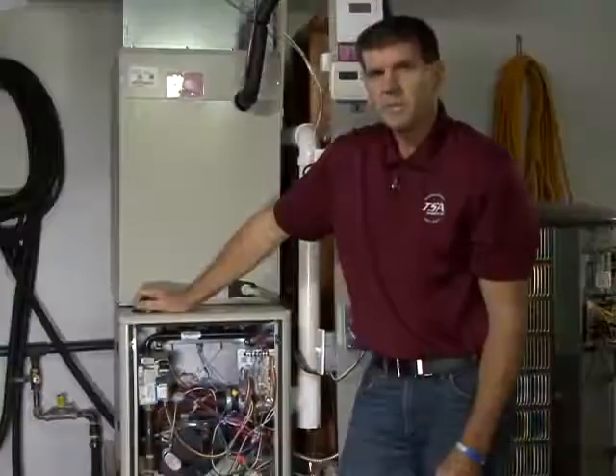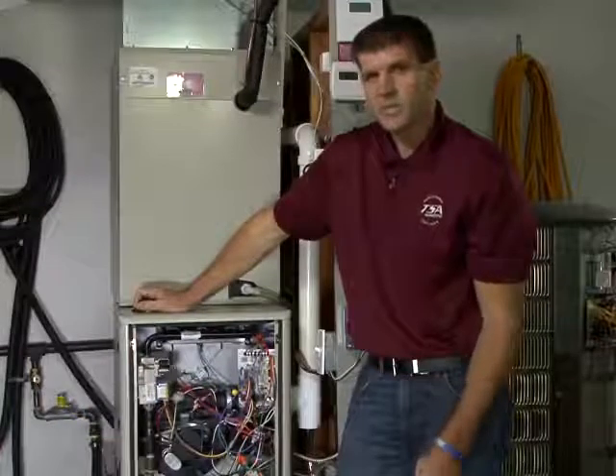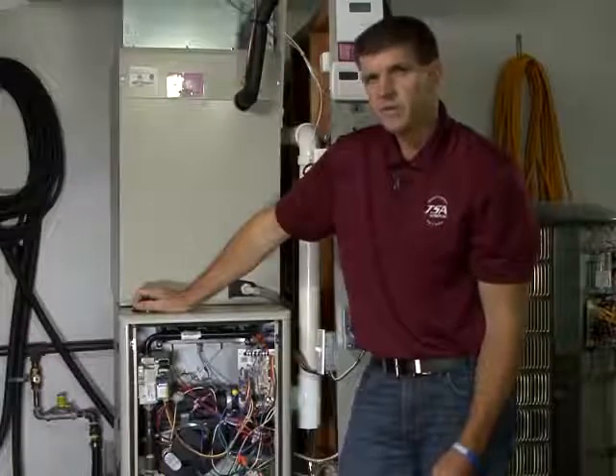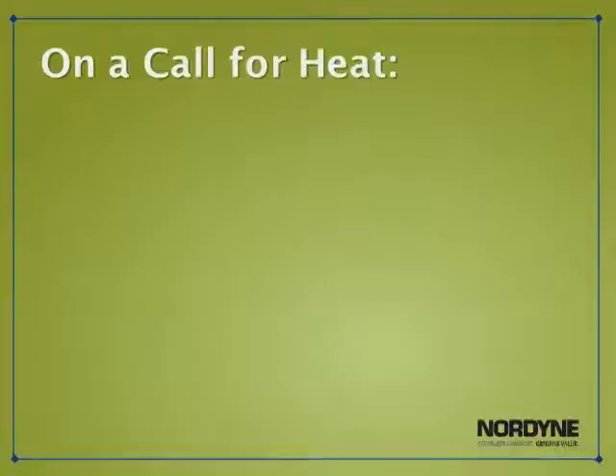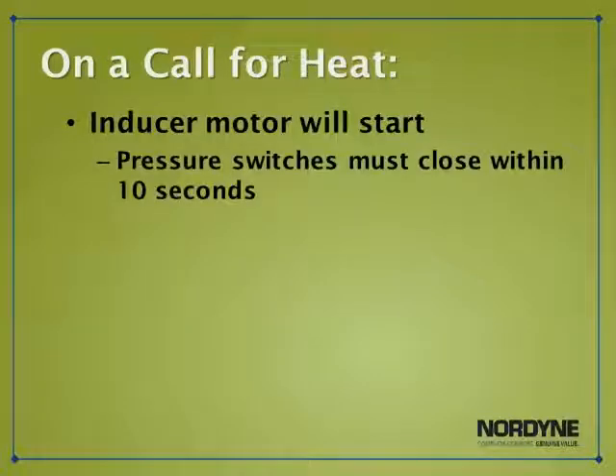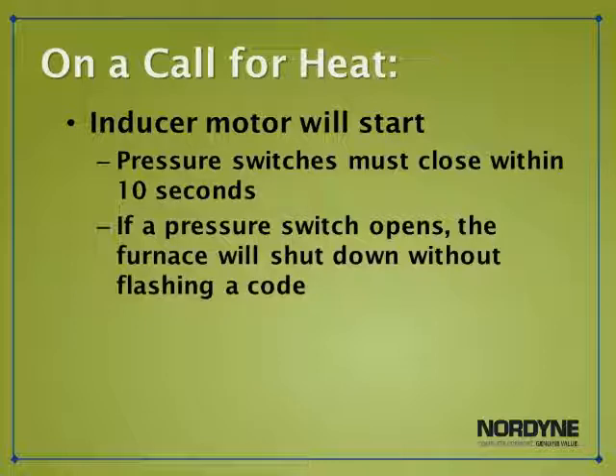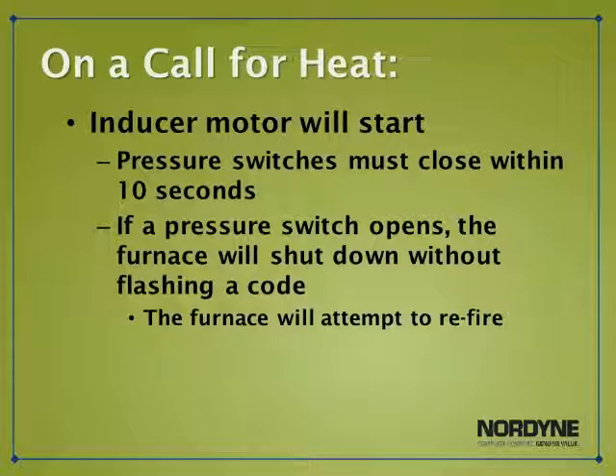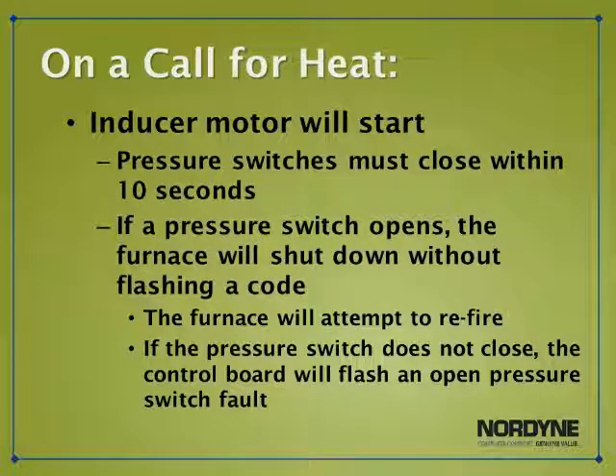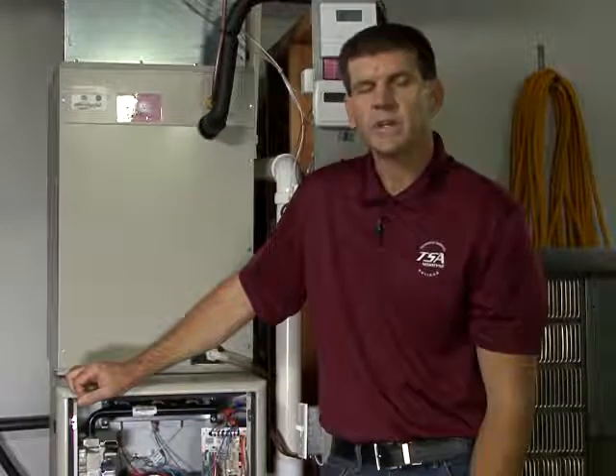All pressure switches are normally open switches. That is, when the inducer motor is off, the pressure switches need to be in open position. For a furnace cycle to start, the interface control board needs to see this open circuit. On a call for heat, the inducer motor will start and the pressure switches must close within 10 seconds and remain closed throughout the entire heating sequence. If a pressure switch opens during the heating process, the board will drop out flames and the furnace will shut down as if you lost a call for heat without flashing a code on the interface board. The furnace will then attempt to refire by starting the inducer motor up and attempt to close a pressure switch. If the pressure switch does not close at that time, the control board will give a flash indicating an open pressure switch. Many times, a blocked condensate line or a blocked flue pipe or undersized flue piping will cause your pressure switch to open and shut down furnace operations.